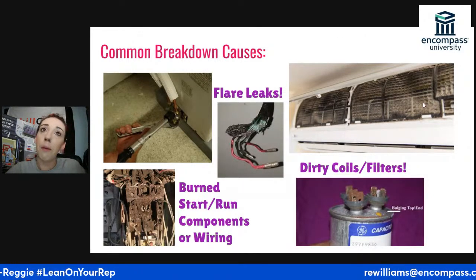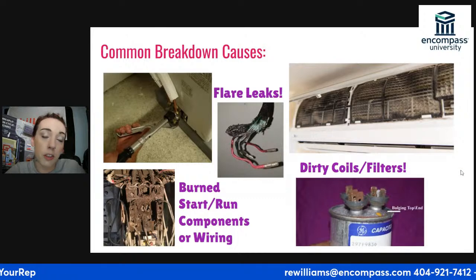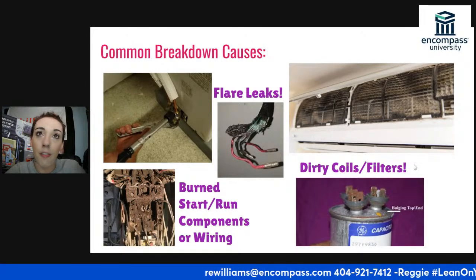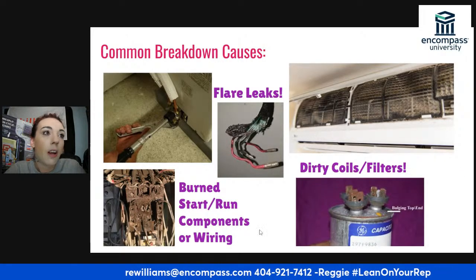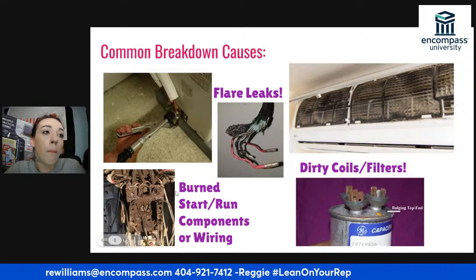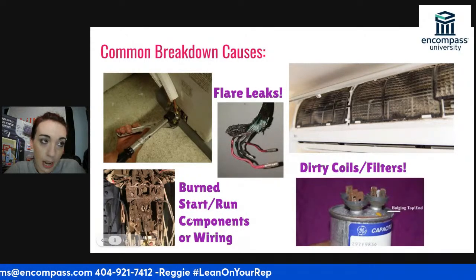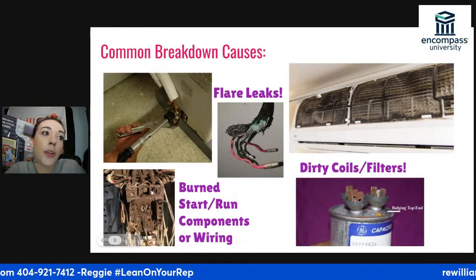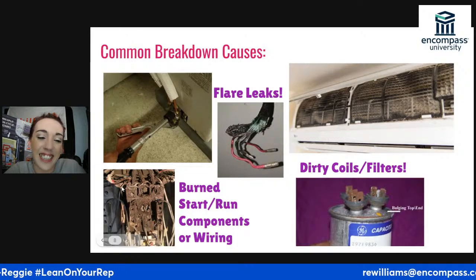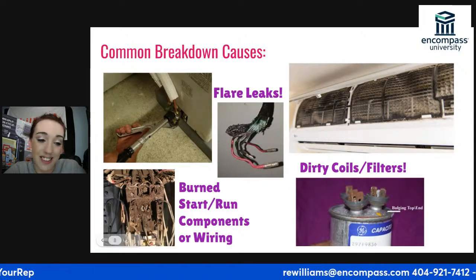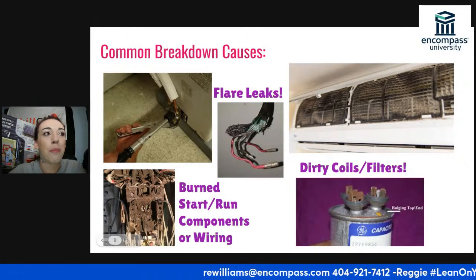Again, pull that blower wheel. A lot of the time, the blower wheel is running slow because it's gunked up with stuff, and that will be a reason for a no cool as well. And then burnt start or run components or wiring. So this is an absolutely cooked contactor. They won't look like this, you guys, I promise. This was just an extreme case.